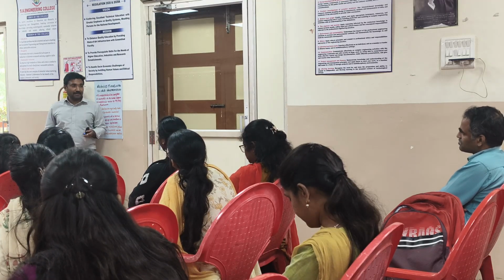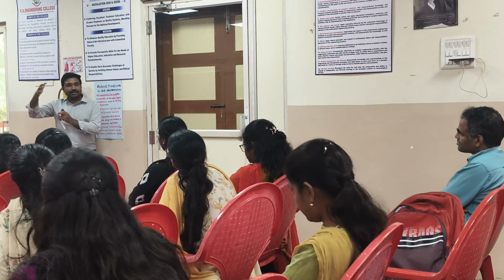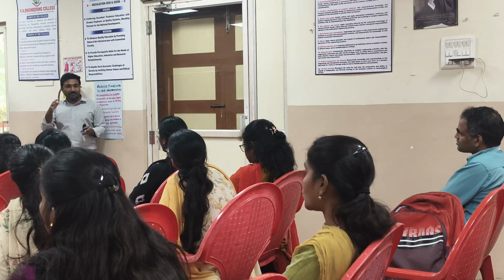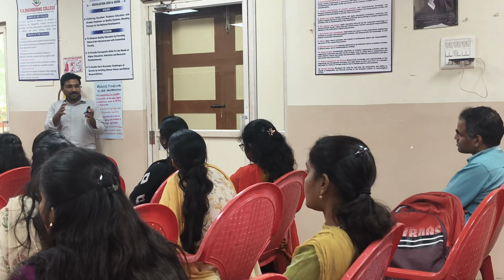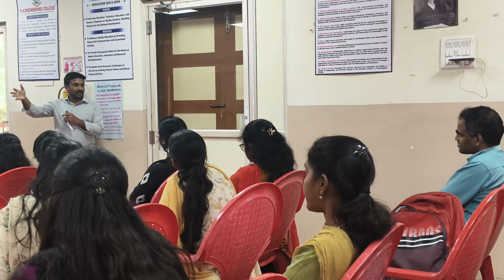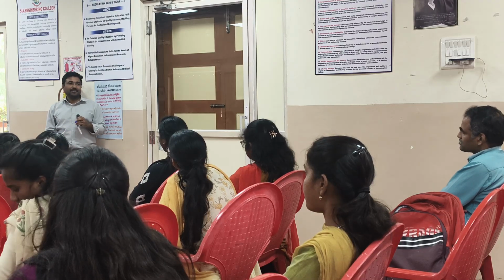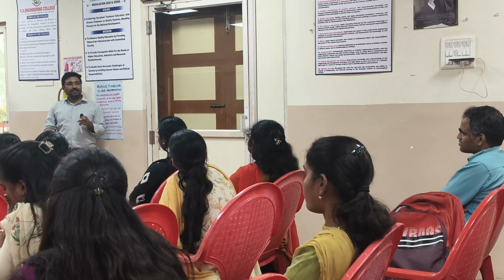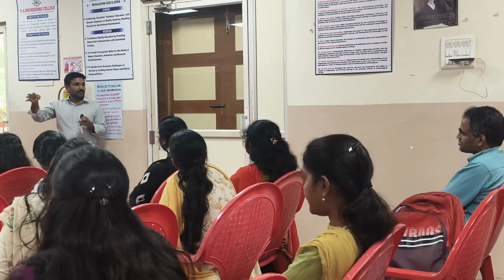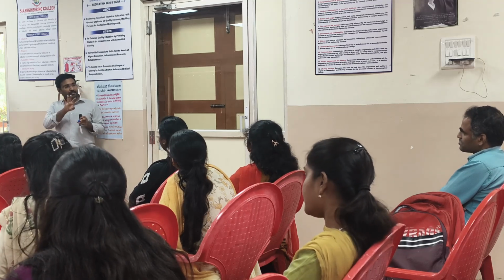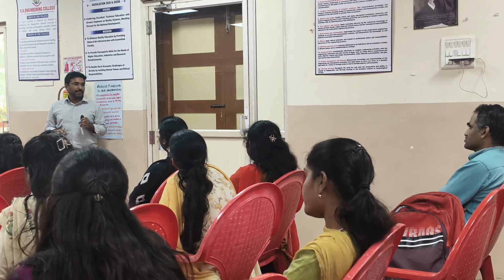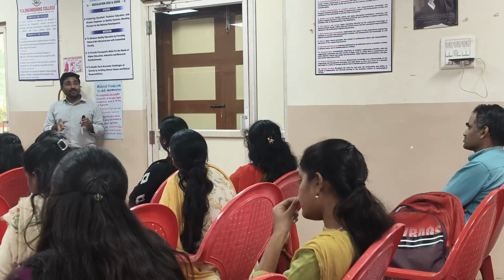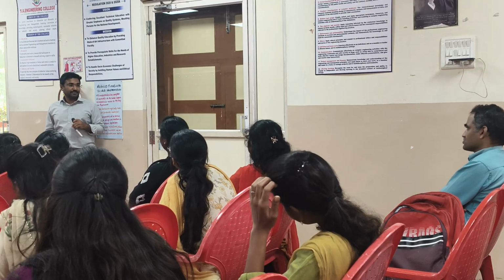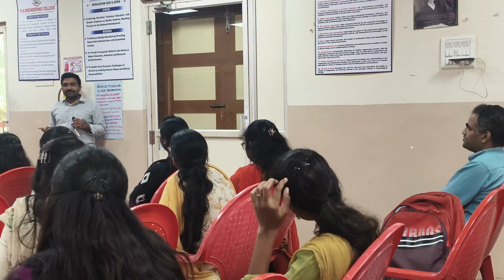So for example, you are connected to 10 loads, immediately you are connected to 20 loads. If the current ripple is less, then the converter cannot give sufficient power to the load, and the voltage will come down quickly. So in all designs, current ripple of 30 to 40% is allowed, but voltage ripple is normally less than 5%. If you meet this requirement, then only we can pass the BIS, the highest standard.